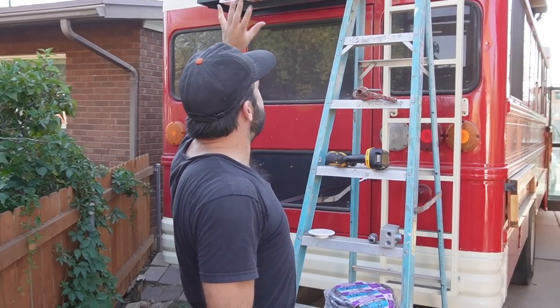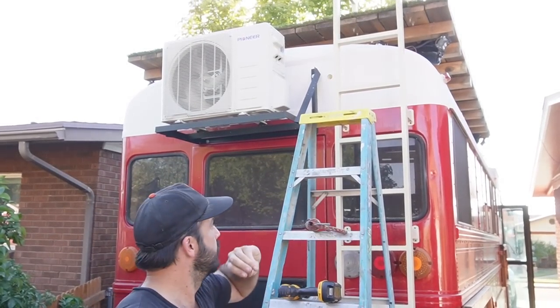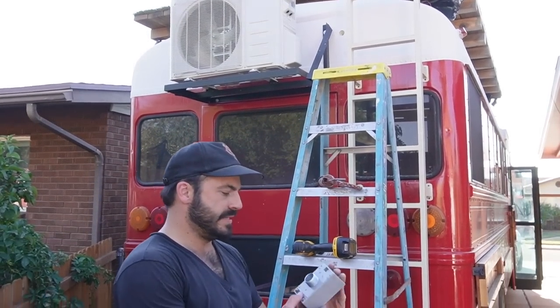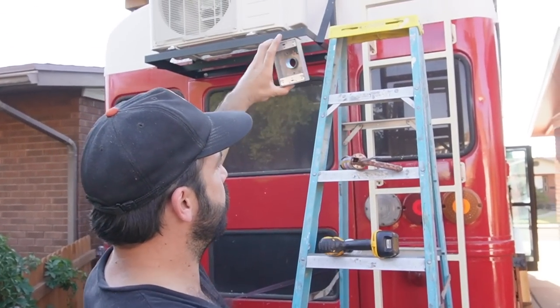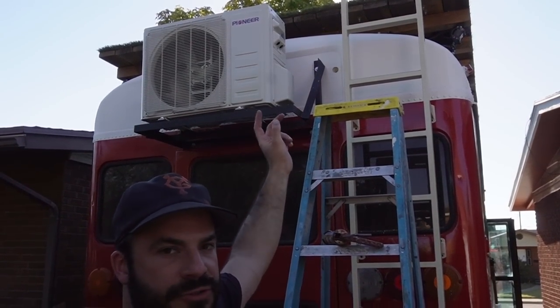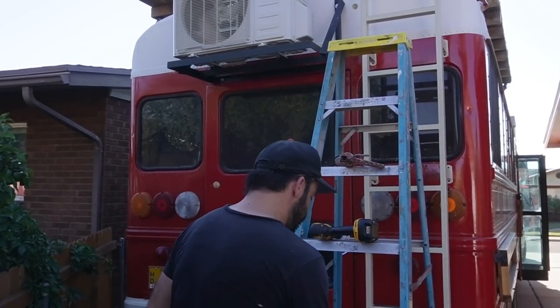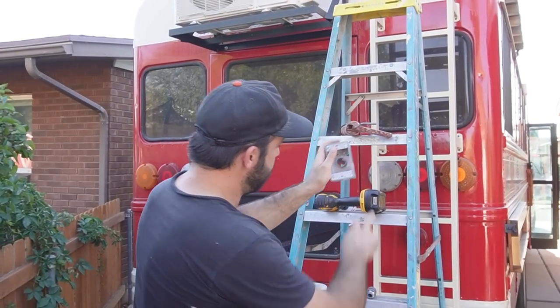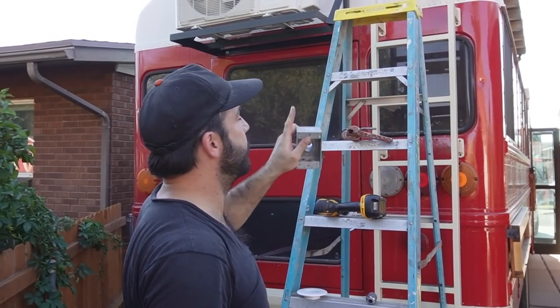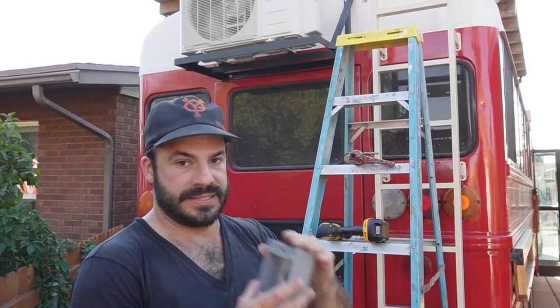Now that we have the exterior unit of our mini-split system mounted, we can start getting ready to make our connections for electrical and refrigerant. We're going to start by installing this outdoor junction box that's going to go right up there where that hole is drilled. This will be how we manage the pass-through of the electrical wires from the interior to the exterior of the bus. Once they enter the junction box, we're going to use some liquid-tight flexible conduit — one length carrying power to the unit and the other carrying the power and control lines from the outdoor unit to the indoor unit.